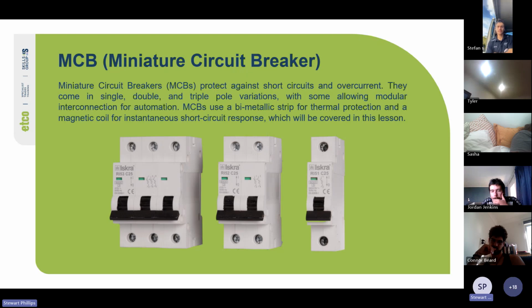So when it talks about allowing modular interconnection for automation, that means if you've got a 25 amp circuit breaker for your three-phase motor, but you've got a 6 amp for your control circuit, you can interlink those. That way if the 25 amp breaker trips, it also kills the 6 amp, and if the 6 amp trips, it kills the power to the 25 amp. So if one trips, the other needs to turn off as well, and you can interconnect those circuit breakers so that they all turn off at the same time.